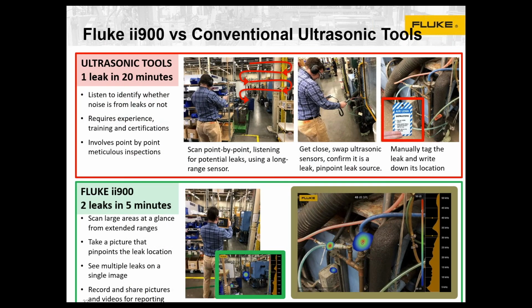Let's take a closer look at how people have typically used ultrasonic tools. In the top box here, there are ultrasonic tools, handheld, perhaps with a wand or parabolic antenna that focuses the ultrasonic information and feeds it into the tool, which translates the ultrasonic down into an audible range the operator can hear. The operator listens and tries to interpret what they're hearing to determine if it's a leak or something else. That interpretation requires experience, training, and certifications. Not only that, rather than inspecting from greater distances, you have to move very close to all the fittings, connections, hoses, etc., make close-up measurements, and then interpret. So it's meticulous and very slow.